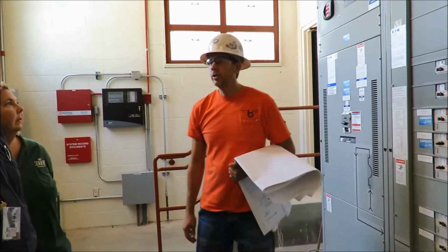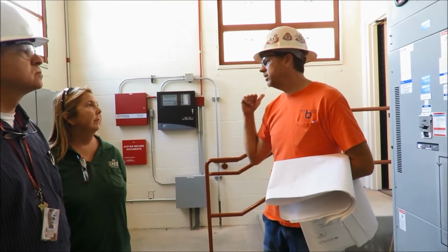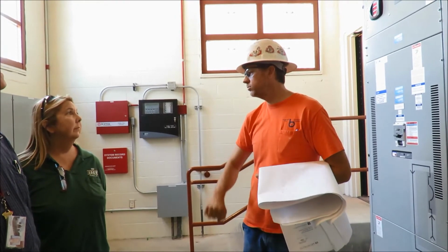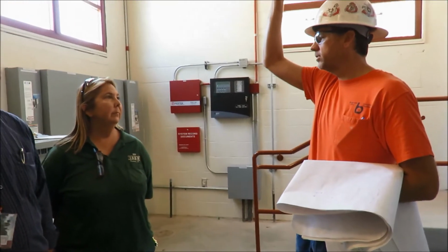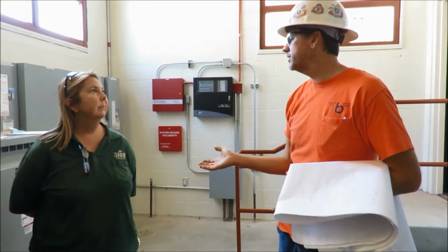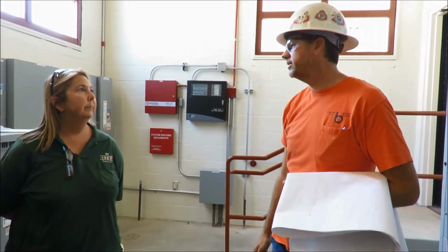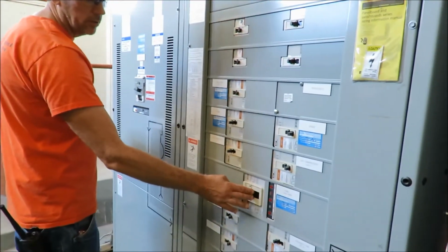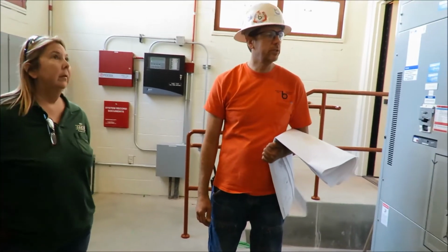Yeah, when we were testing, what I did, I opened the breaker that's in HPV1 inside the electrical room on the north side here. That was the easiest way. All the lighting in the building, because that's feeding all the sub panels, they're stacked up. So if I turn that off, you will see all the emergency lighting if you ever want to test it. That's the easiest way I see. You could do it here too, same thing, but I just did it that way. Yeah, so there's two ways to skin that cat.